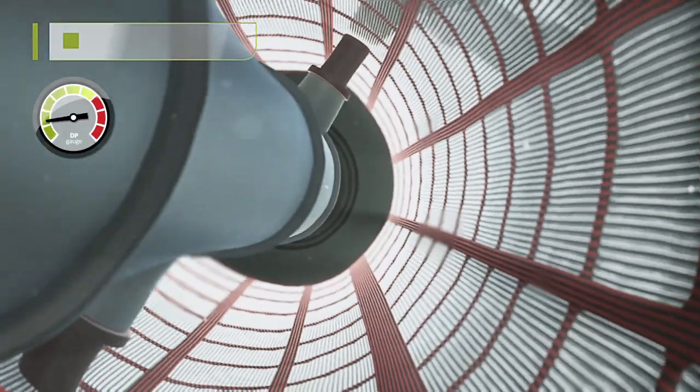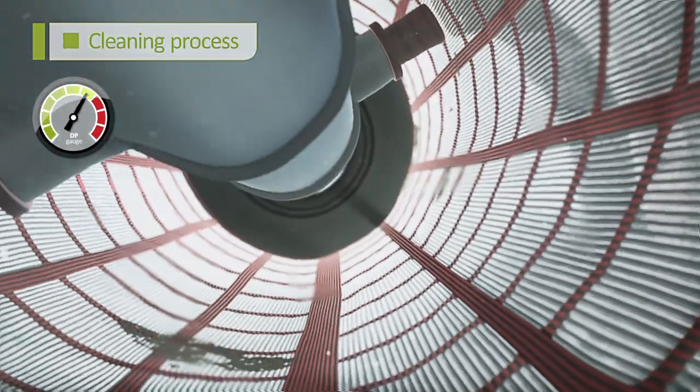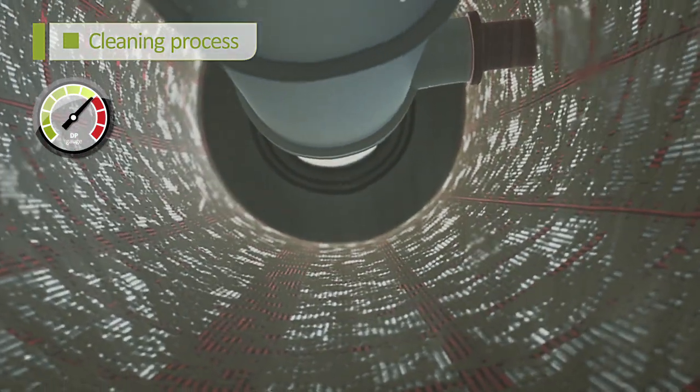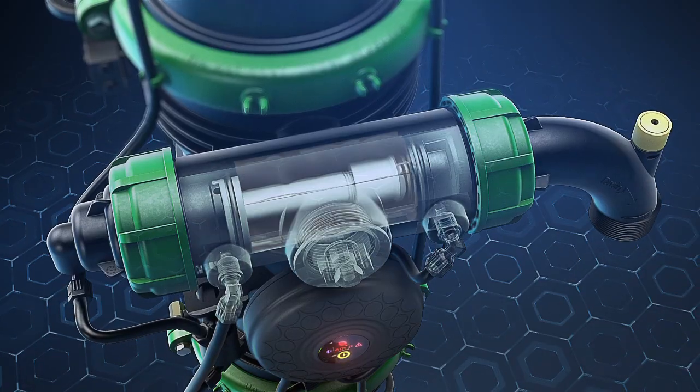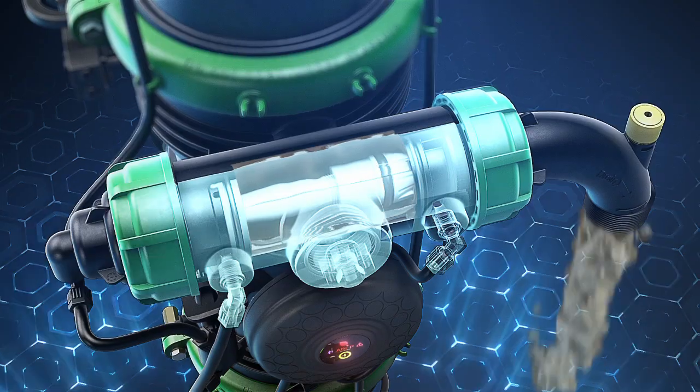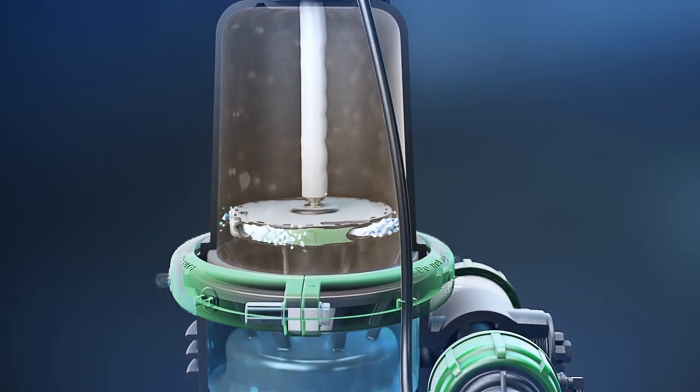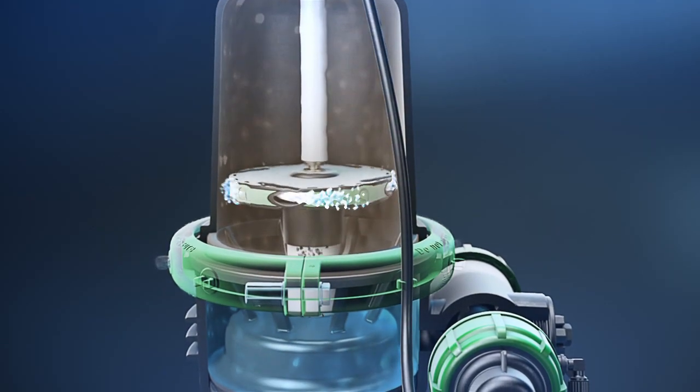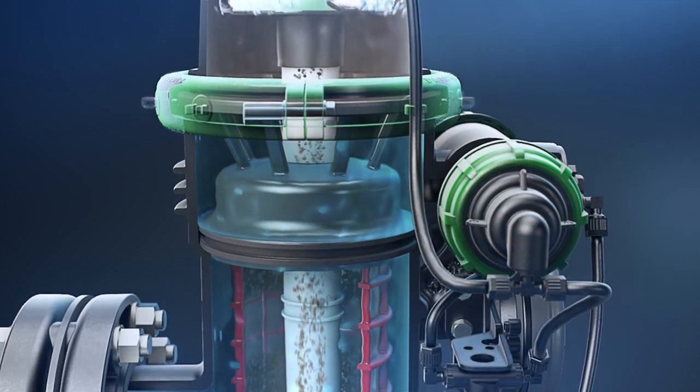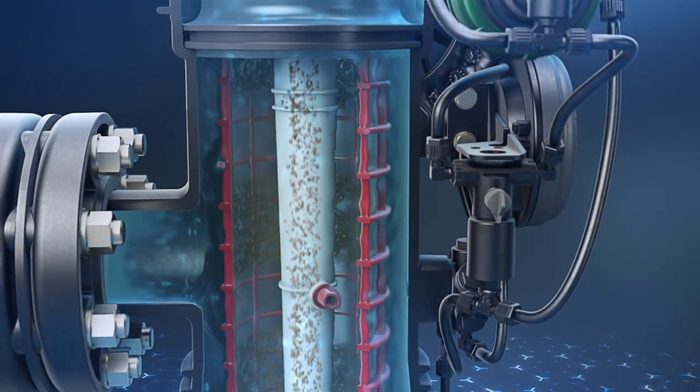The cleaning process begins when the pressure differential reaches a preset level and the system activates its self-cleaning cycle by opening the flushing valve. A strong suction force at the scanner nozzles effectively removes the dirt particles from the screens.